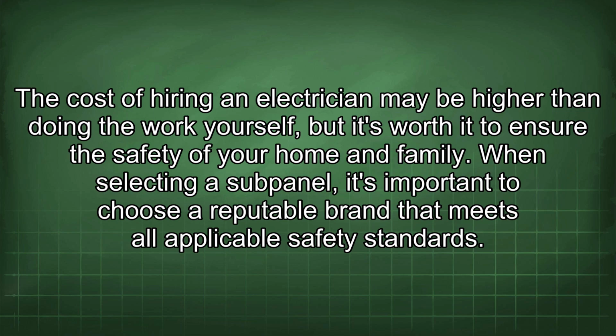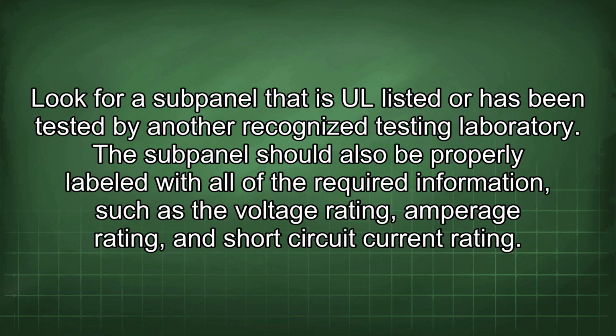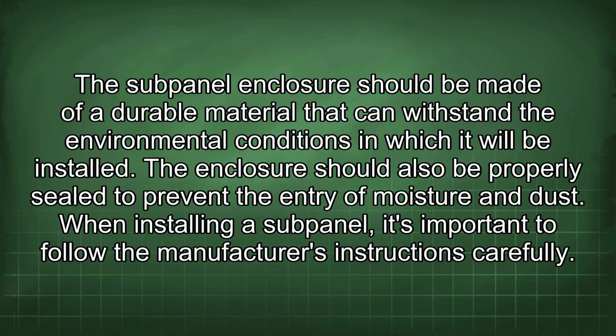When selecting a subpanel, it's important to choose a reputable brand that meets all applicable safety standards. Look for a subpanel that is UL listed or has been tested by another recognized testing laboratory. The subpanel should also be properly labeled with all of the required information, such as the voltage rating, amperage rating, and short circuit current rating. The subpanel enclosure should be made of a durable material that can withstand the environmental conditions in which it will be installed. The enclosure should also be properly sealed to prevent the entry of moisture and dust.